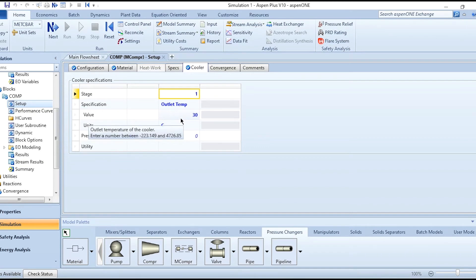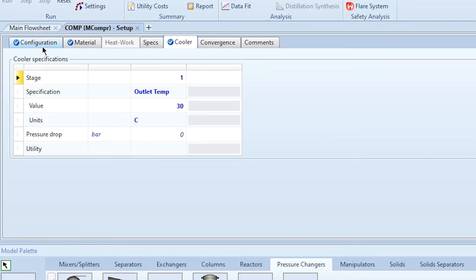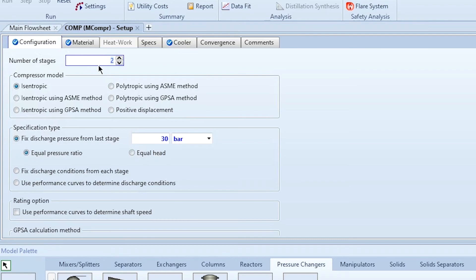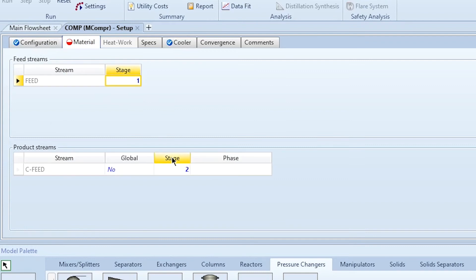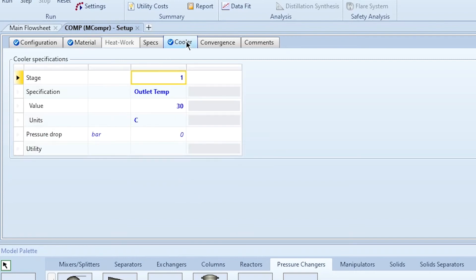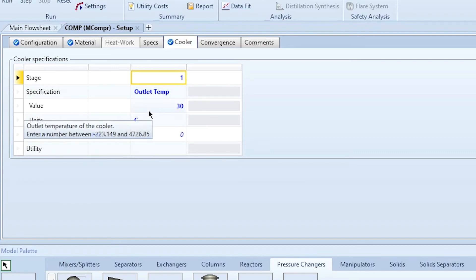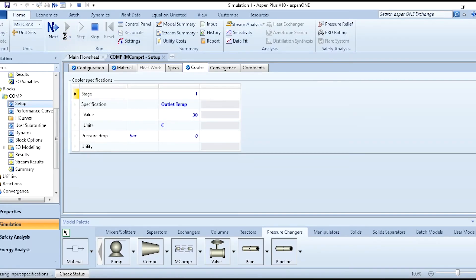This outlet temperature value corresponds to the methane or any other media used in the multi-stage compression system. If you want to simulate three stages, change the number of stages to 3 and keep Equal Pressure Ratio. Then go to Material and update the product to exit from stage 3. The rest of the settings remain the same. If the outlet temperature is unchanged, click Run again and the results will be updated.